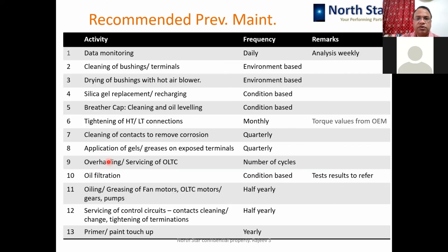Recommended preventive maintenance schedule: data monitoring frequency is daily or on a continuous basis. If you have the devices, you can monitor the data uninterrupted, and the data is to be analyzed at least on a weekly basis. Then cleaning of bushing terminals, drying of bushings with hot air blower based on environment: if the humidity is high in rainy days, then you can dry the bushing very often. This bushing drying with hot air blower is sometimes very important where your cable box is air filled and the humidity is high.